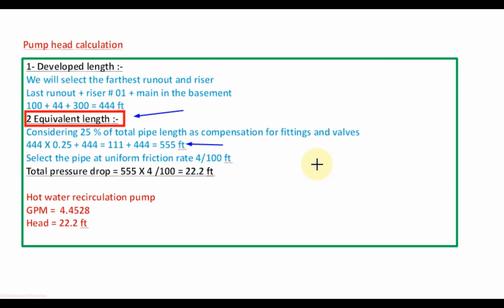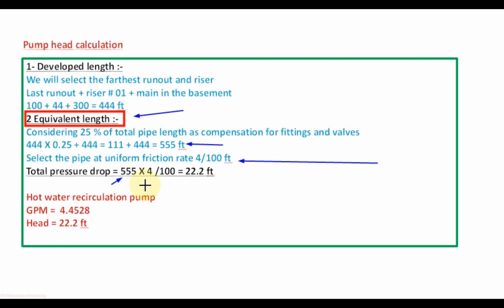We will design the hot water recirculation piping at a uniform friction rate of 4 feet per 100 feet. The total pressure drop equals the equivalent length of 555 feet multiplied by the friction loss rate of 4 feet per 100 feet, giving a total pressure drop of 22.2 feet.